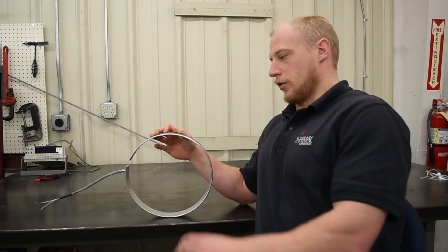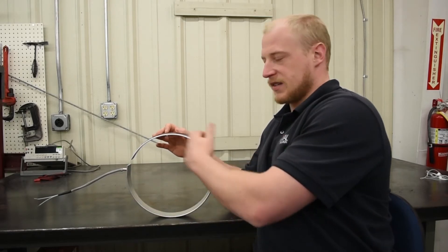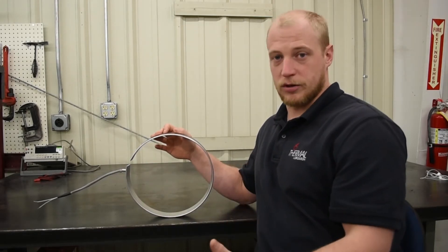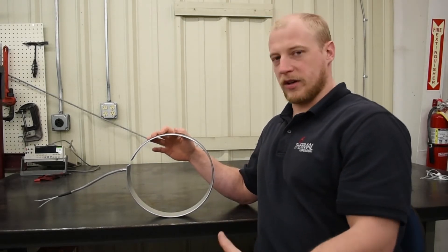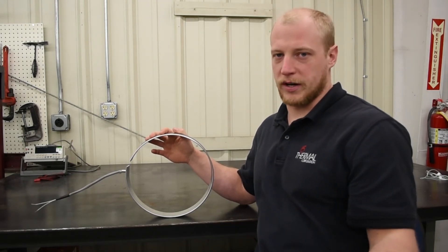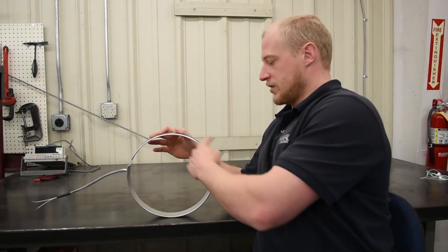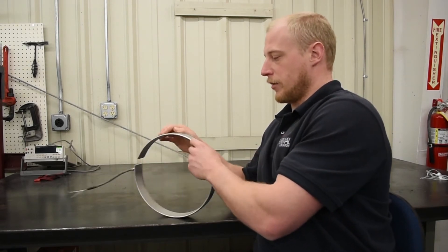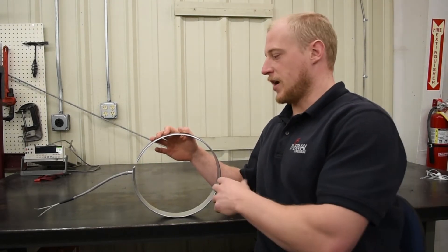So we've got this heater, we know the size, we know what temperature we're running at. We can look at one of those graphs and say it's going to lose three watts per square inch to the atmosphere. Then we calculate the surface area of our heater, multiply that by three, and that's the amount of wattage that's going to be lost to space.